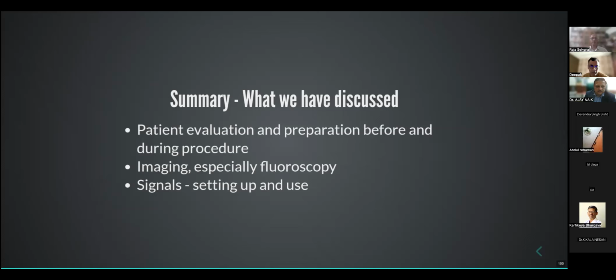If you have noise in an individual patient, either during ablation or without ablation, I think you have to check each source. So what we do is keep disconnecting everything that is there on the patient and see when you disconnect something, the noise will come down. See if the table is earthed well, every equipment is earthed. Disconnect the pulse oximeter, see if that makes a difference. Disconnect the other monitors, disconnect the defibrillator, and you'll usually find that it's something from there.